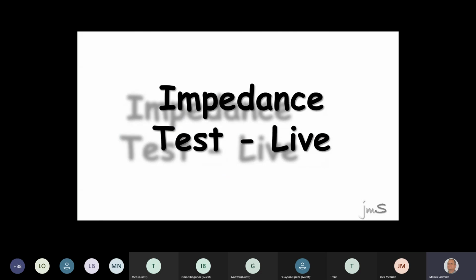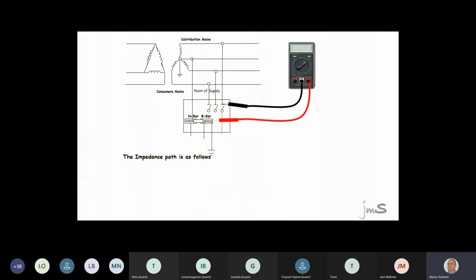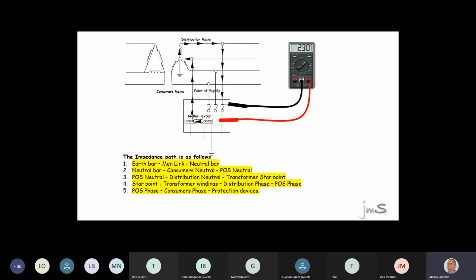Let's check live. Guys, I'm going to go to a circuit where there's no plug. Now, firstly, if you're an inspector, is it true that you're going to check the switchboard? Because remember, that is also an impedance test. And here we go. We're going to do a test from the earth all the way to the transformer and all the way back. There's your impedance test. Your tester will give you a voltage. Happy with the voltage? Now, I want you guys to take out your calculators. At the switchboard, type in 230 volts, voltage. Now you're going to divide it by the ohms. The ohms is 0.98. So it's 230 divided by 0.98.